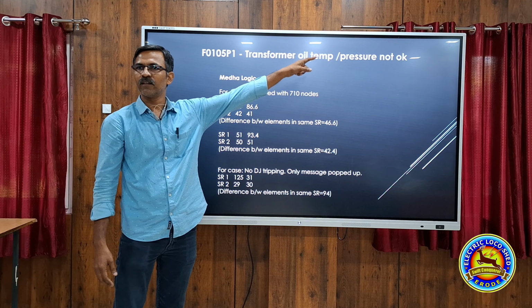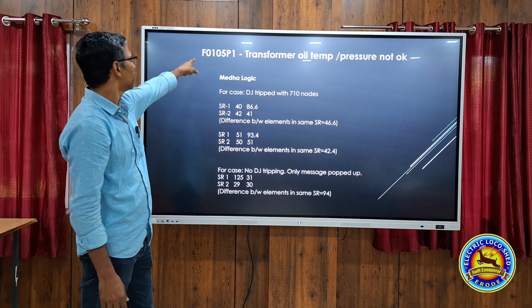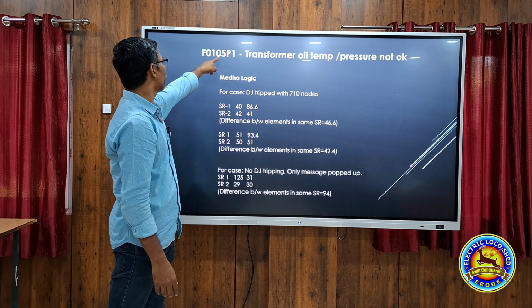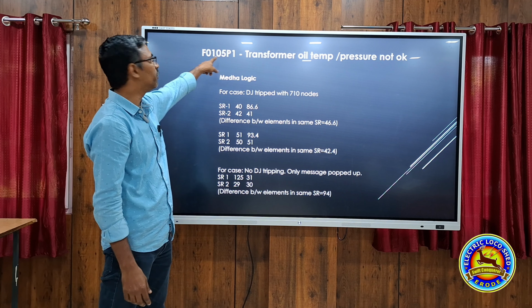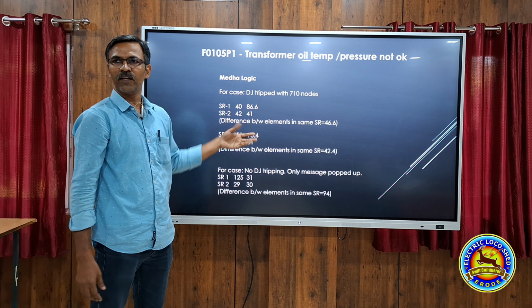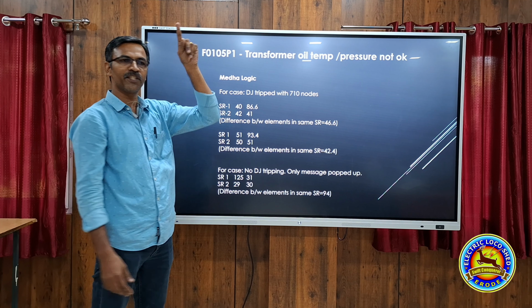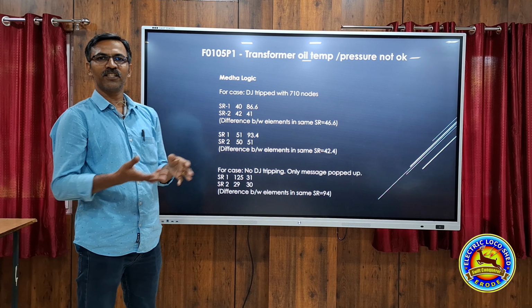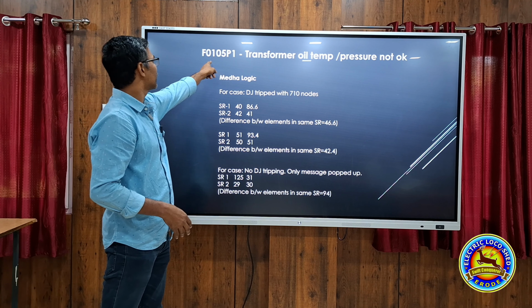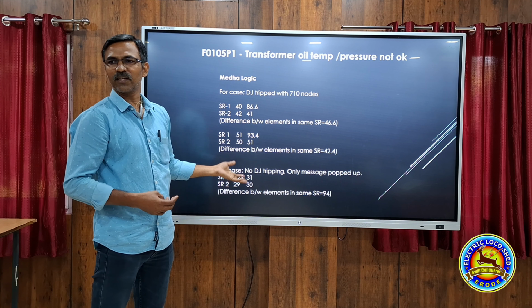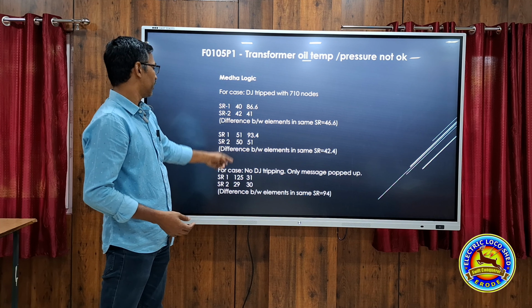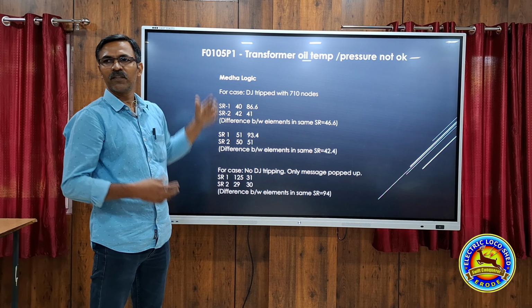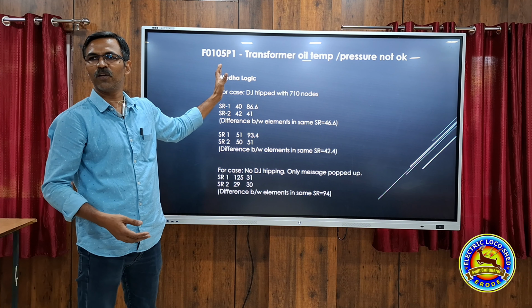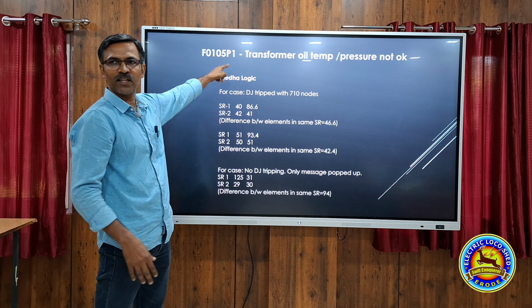What is the problem with this message? The message is F0105 P1. Actually, it should be P2 because DJ is not tripping. For every P1 message, DJ should trip. But the problem with the logic is there is no P2 fault for this kind of problem, only P1 fault. DJ will not trip, but this message will come. The loco pilot will get confused, and he will trip the loco and say P1 fault has occurred.